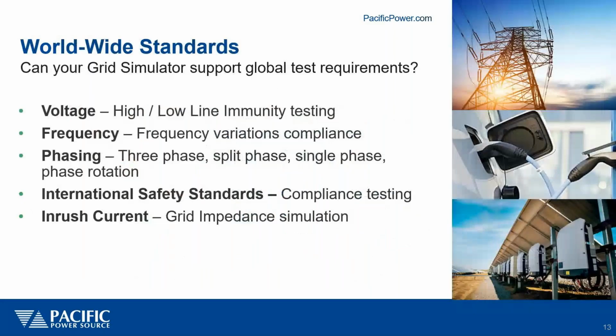So when it deals with AC power, grid simulators support all kinds of grid permutations - voltage and frequency, as well as power levels, depending on the size of your products, as well as potential for managing inrush current and requirements for different load conditions. That includes voltage, frequency, phasing - three-phase, split-phase, single-phase combinations, depending on what kind of grid connection your product requires, as well as phase rotations. Positive or negative phase rotation can be tested with a grid simulator.